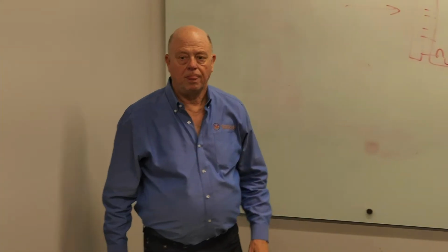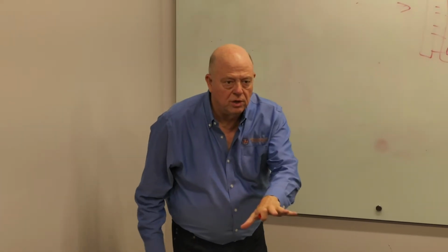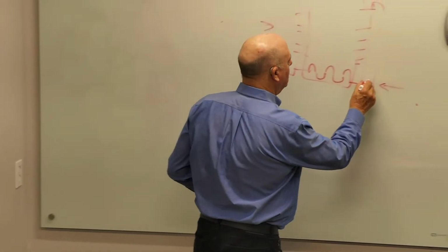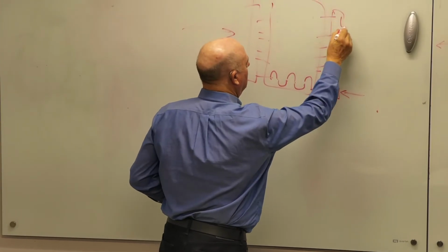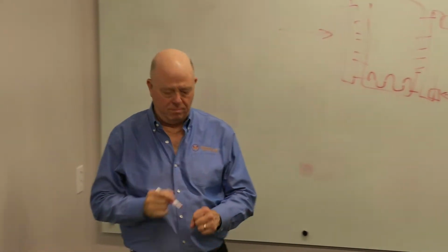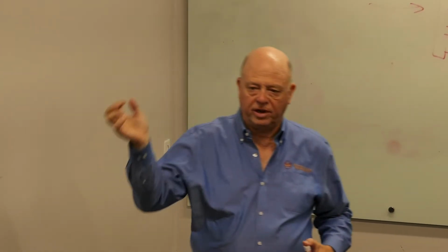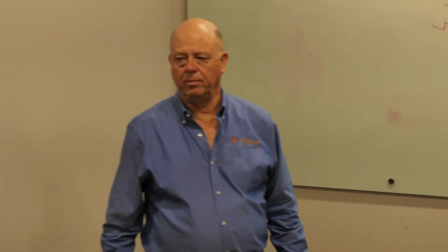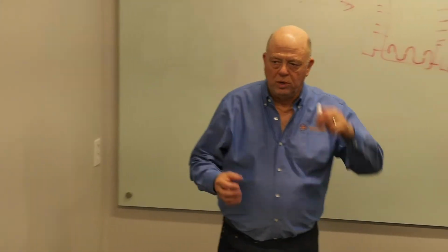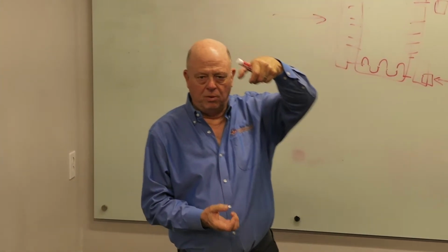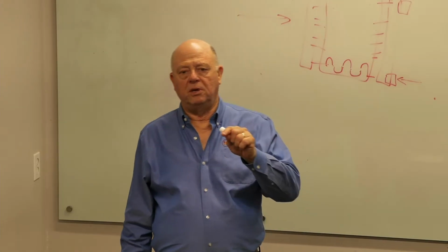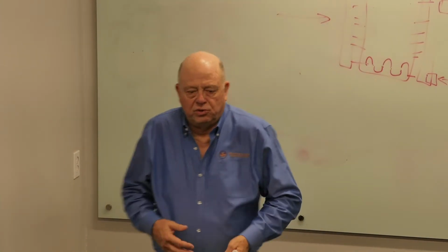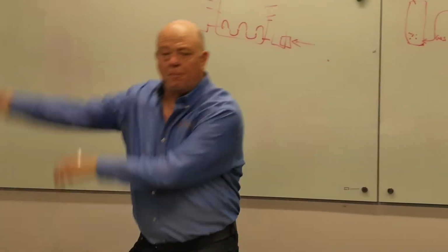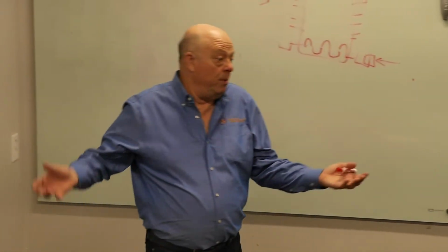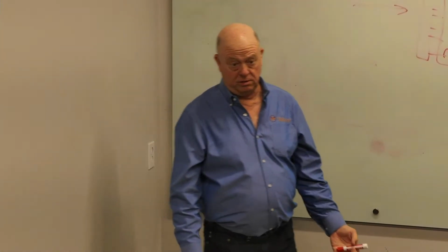Now, most air handler coils that you'll have on your jobs will have a coil hookup both at the top and the bottom. And you'll have to cap one and use the other. The reason that you usually will have them on both the top and the bottom is because they'll use the same coil, whether it's a right-hand connection on the air handler or a left-hand connection. They just flip the coil over. That way the manufacturer only has to make one coil design.